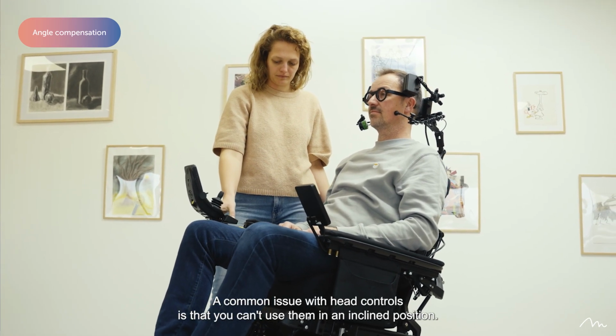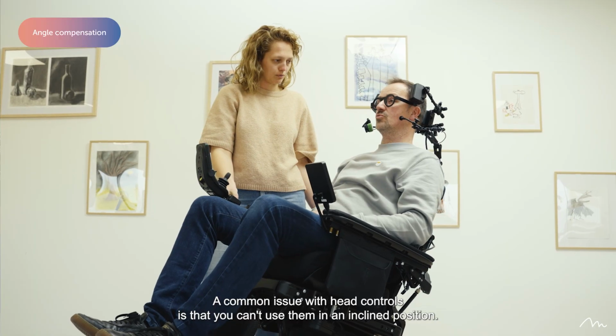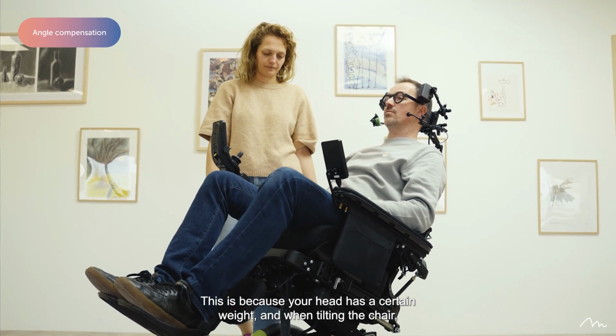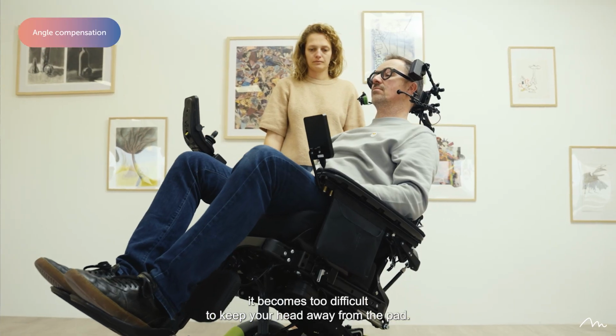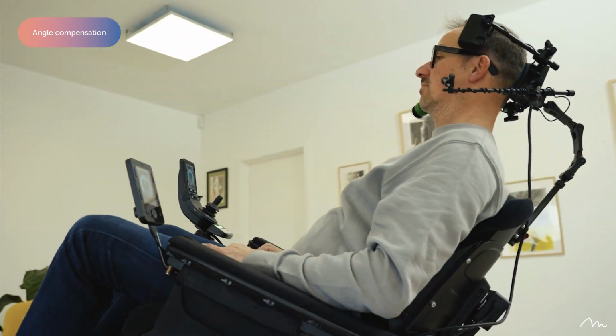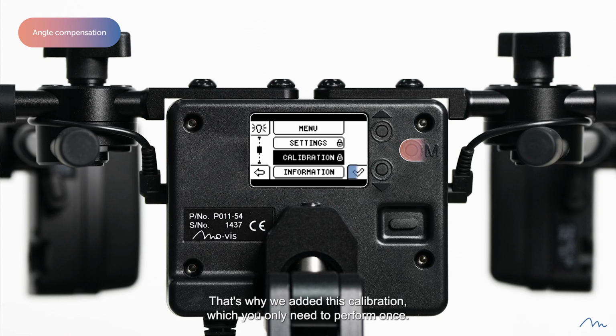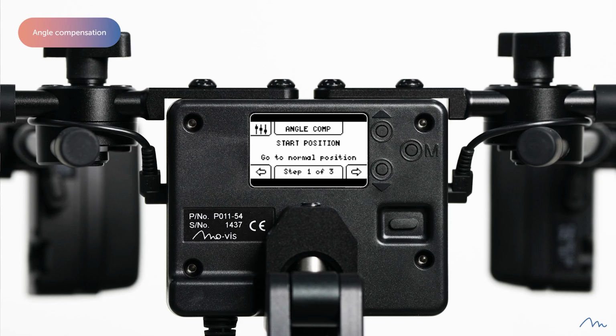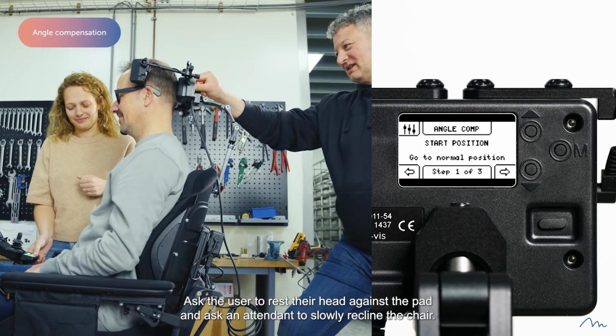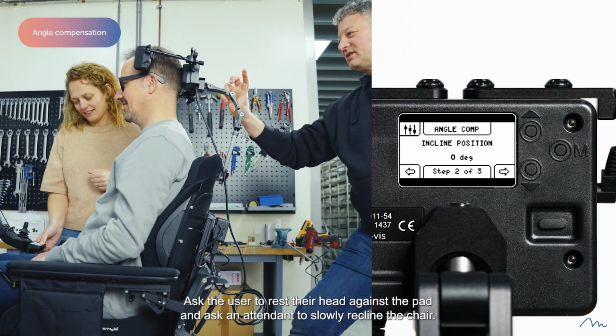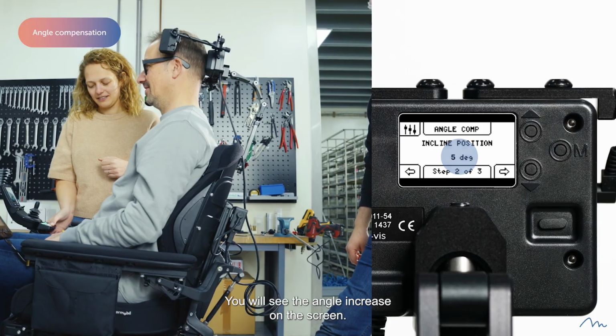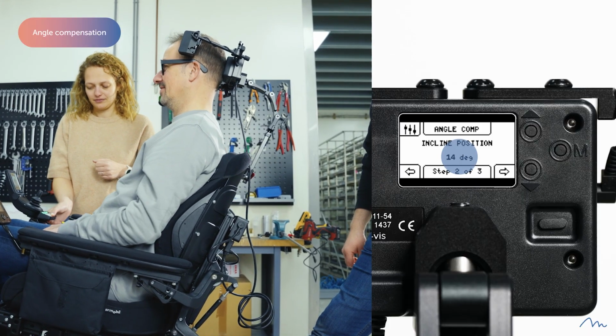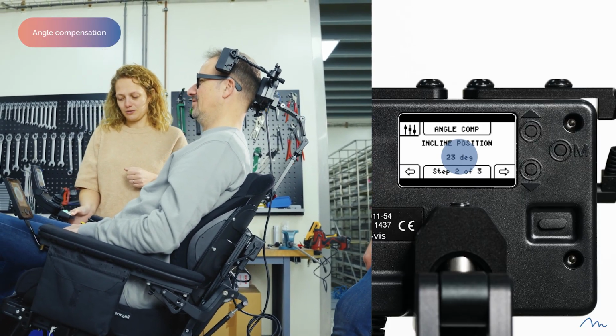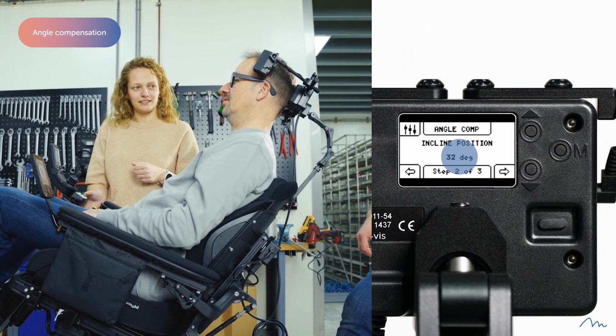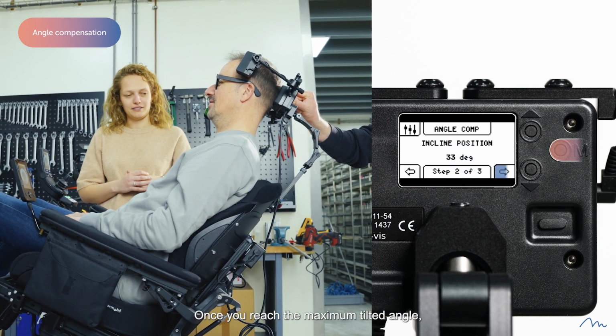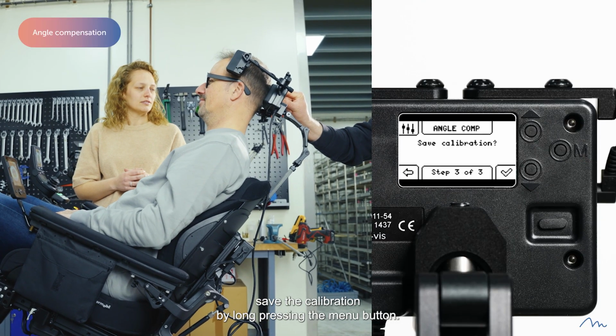A common issue with head controls is that you can't use them in an inclined position. This is because your head has a certain weight, and when tilting the chair, it becomes too difficult to keep your head away from the pad. That's why we added this calibration, which you only need to perform once. Ask the user to rest their head against the pad and ask an attendant to slowly recline the chair. You will see the angle increase on the screen. Once you reach the maximum tilted angle, save the calibration by long pressing the menu button.